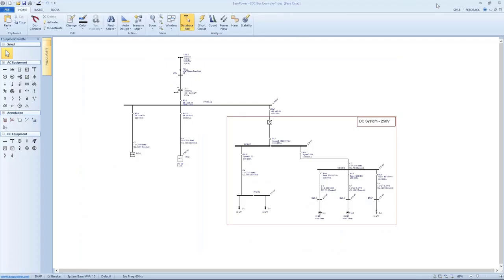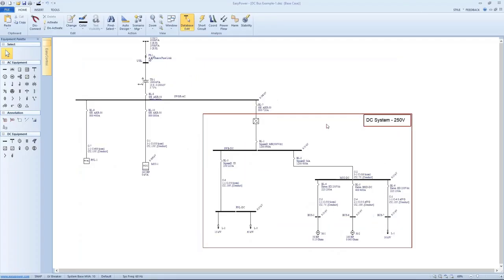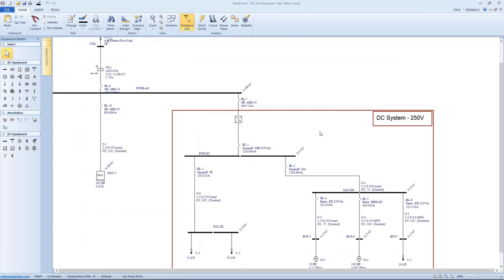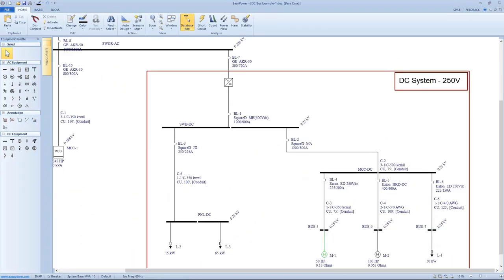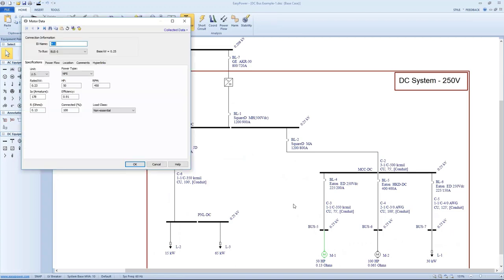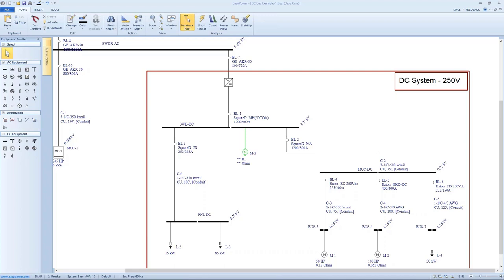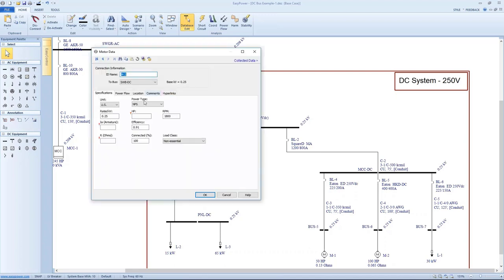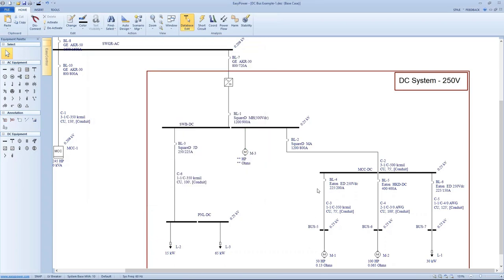So I'm in the database edit and I want to look at a few of these components. Let's start with a motor. And again, as we set up a new motor in EasyPower, what it's going to ask for is the horsepower and the armature impedance. Let's just kind of do that. Now, one of the things you'll find is if you try to apply an AC equipment, piece of equipment to the DC side of the system, you will get pulled up short and the tool will ask you if you know what you're doing. So what we're looking for is the horsepower and the armature current or resistance. And based upon that, we can model, if you will, the short circuit model for the motor.